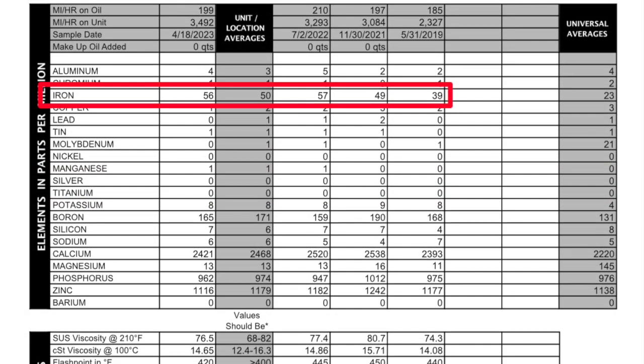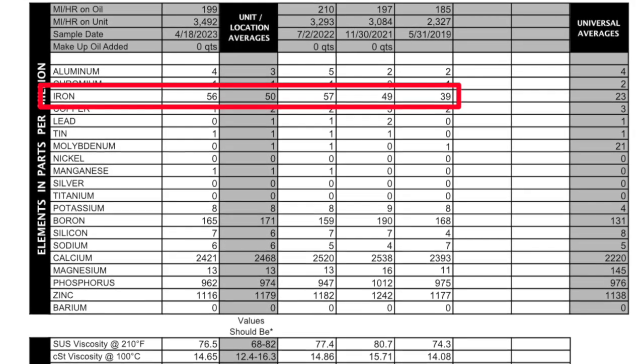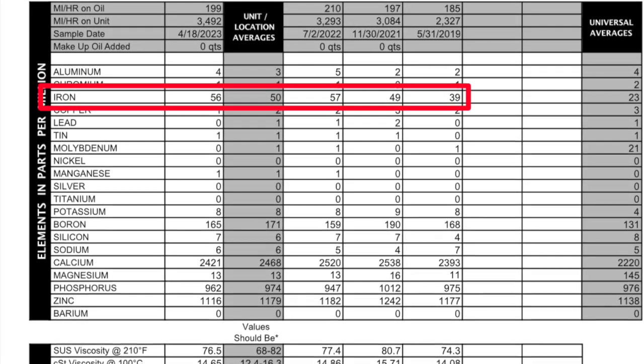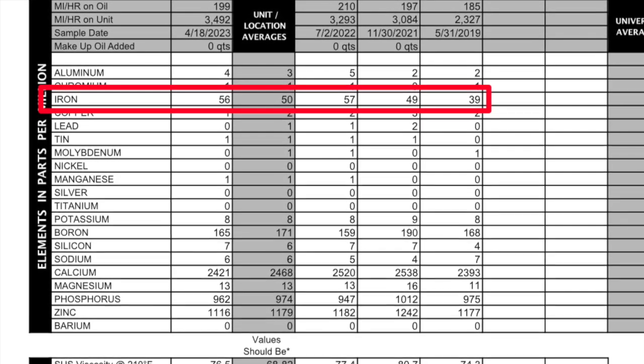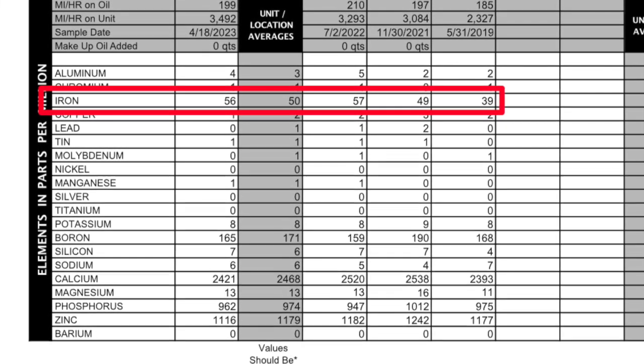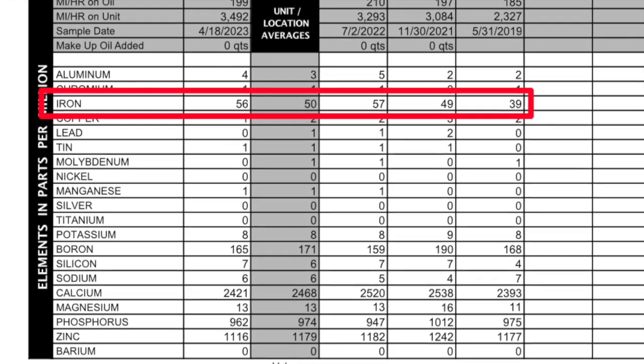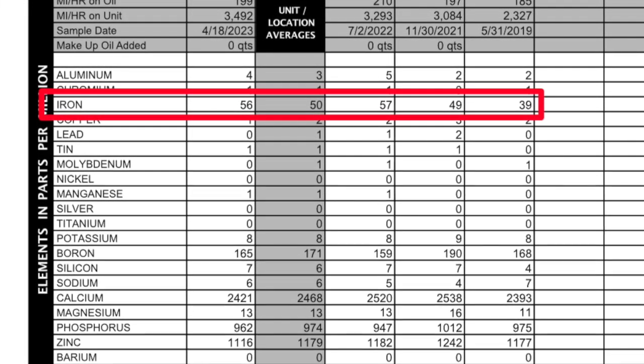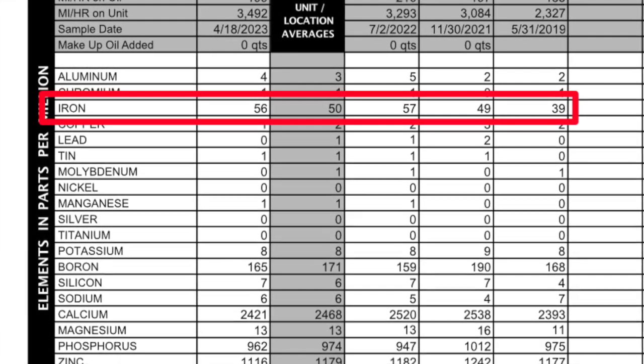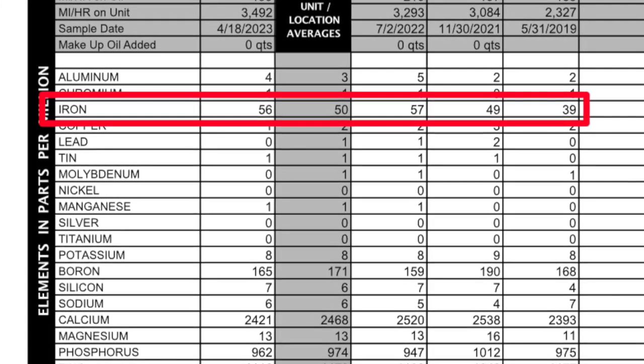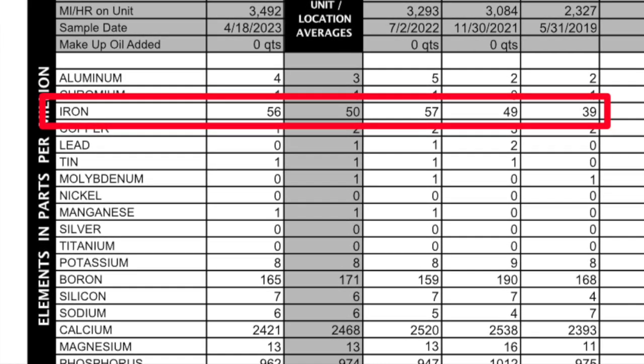Now I showed you potassium that was dead even — here's the iron, which went from 39 to 49 to 57. This was a concern of mine because it was on the rise, and this is exactly the kind of thing you want to do oil analysis for: to see trends where things are starting to go up, because those things are concerning. In this particular case, I knew I had started changing how I ran the six kilowatt generator because of the lithium batteries — we were loading it differently and running it in different circumstances — so I expected a little bit of change, but I was still concerned.